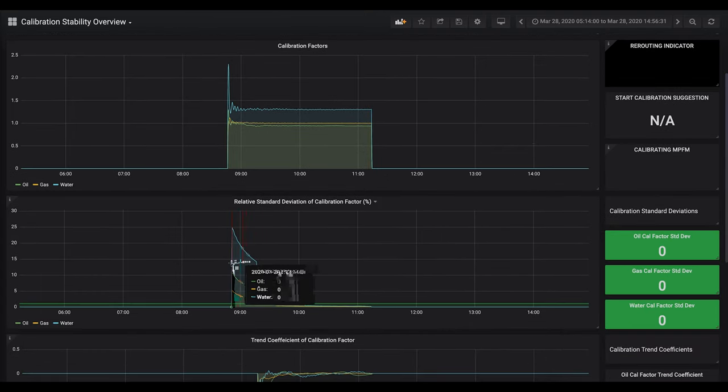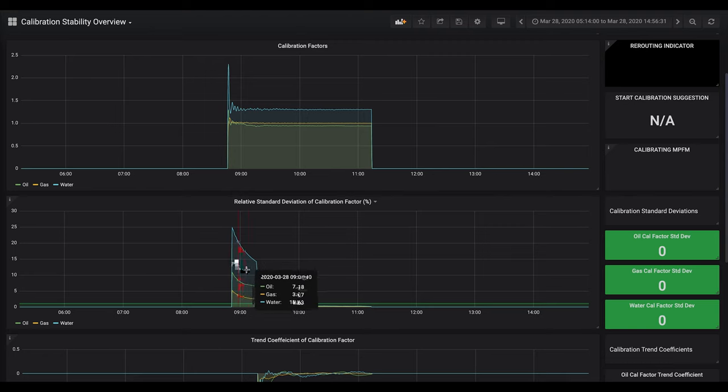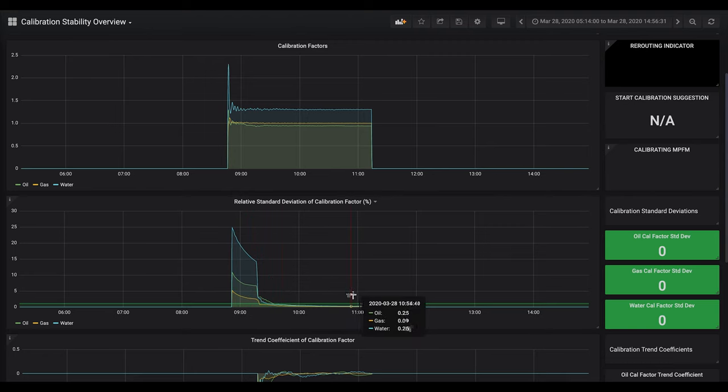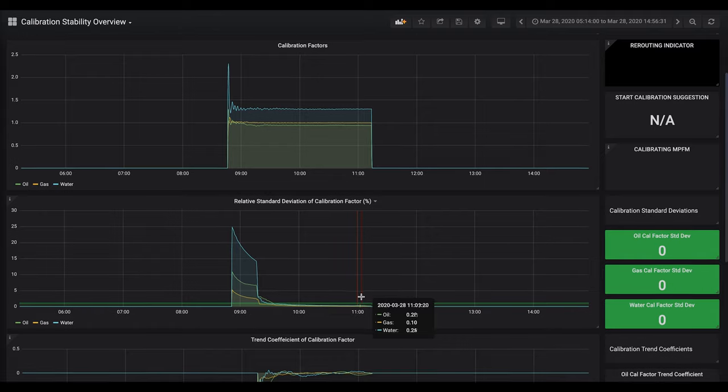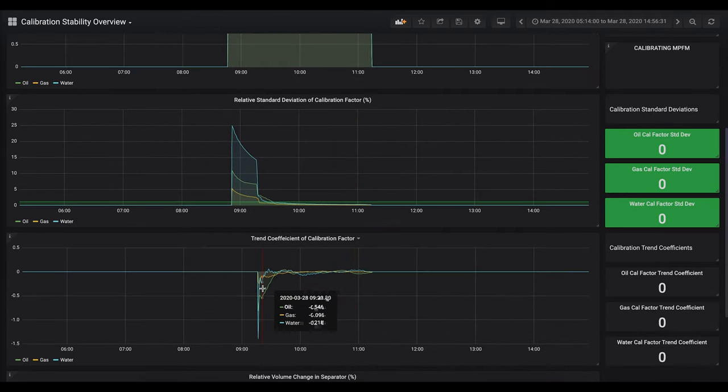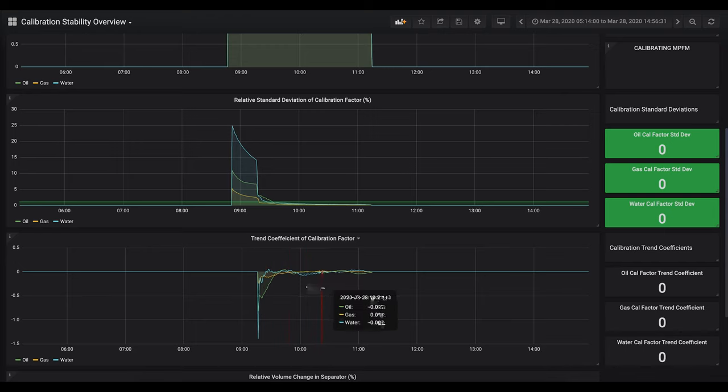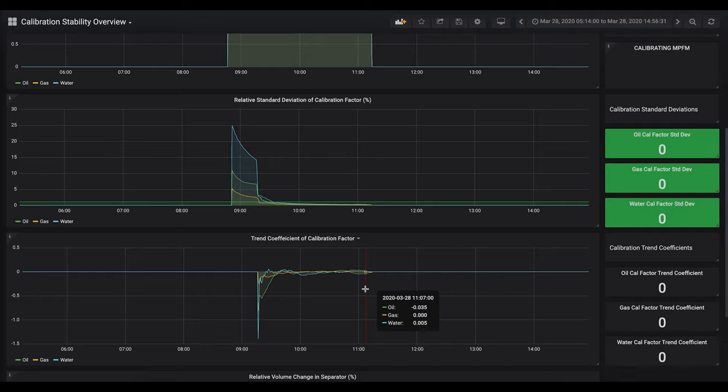Beneath that we have a live calculation of the standard deviation of that calibration factor. You can see this decreases over time leading to a more certain result. Beneath that we have a linear trend calculation which is just showing the trend of the calibration factor. Again, we want this to get as close to zero as possible.